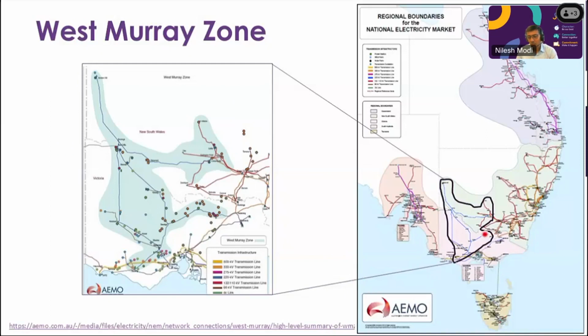This West Murray zone network consists of the areas of Southwest New South Wales, which is here, and Northwest Victoria. It has a large number of inverter-based resources connected: wind farms, solar farms, batteries. There are SVCs in there and HVDC links, so it's kind of a perfect storm for inverter-based resource interaction. It is largely a radial 220 kV network, in a weak part of the network. More recently, there has been some installation of synchronous condensers in that part of the network, which has improved the system strength or grid strength in that part of the network.